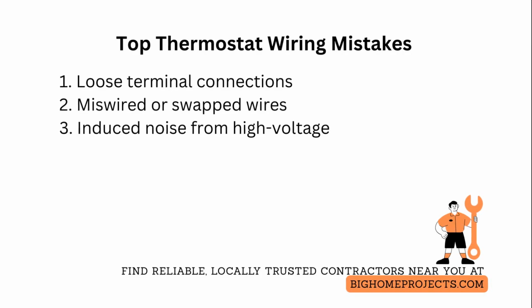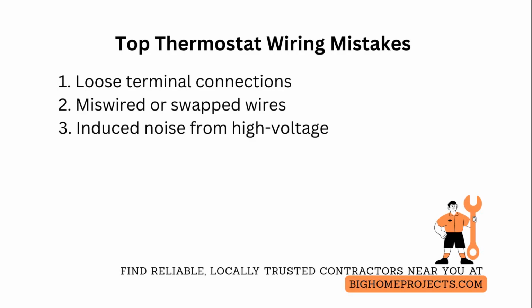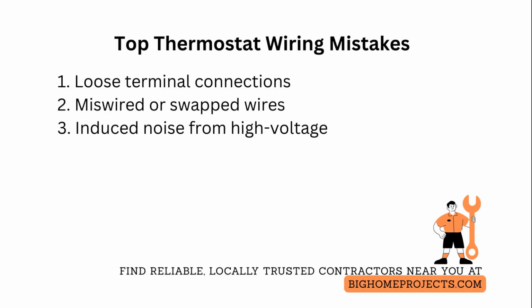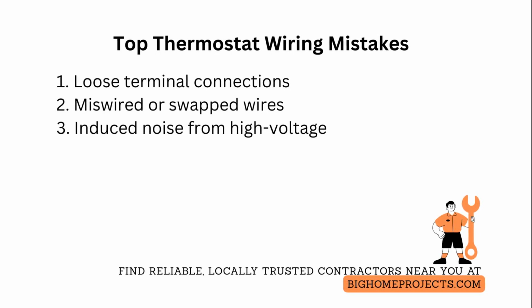Third is running thermostat wire alongside high voltage lines, which induces noise and erratic control signals. Remedy by rerouting the wire at least 12 inches away or using shielded thermostat cable and grounding the shield properly.